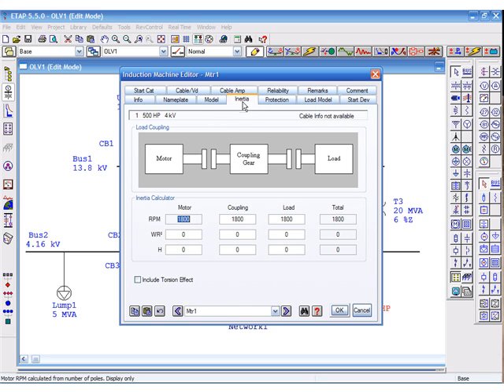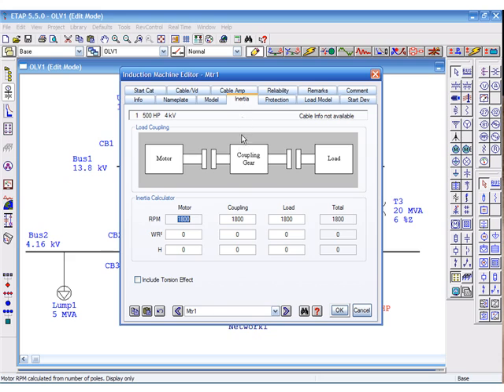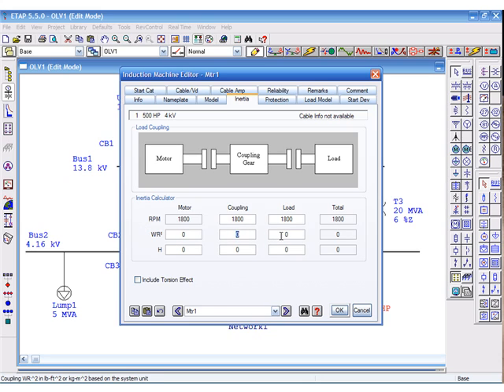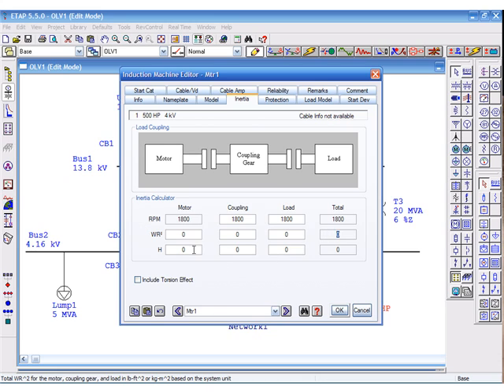The next piece of the information is WR squared, or WK squared, for the motor coupling gear and the load. If these are individually available, the total is shown in the total column. If the values are not known individually, but as a total shaft, they can be entered in any of the fields. ETAP uses the total value for the acceleration study.